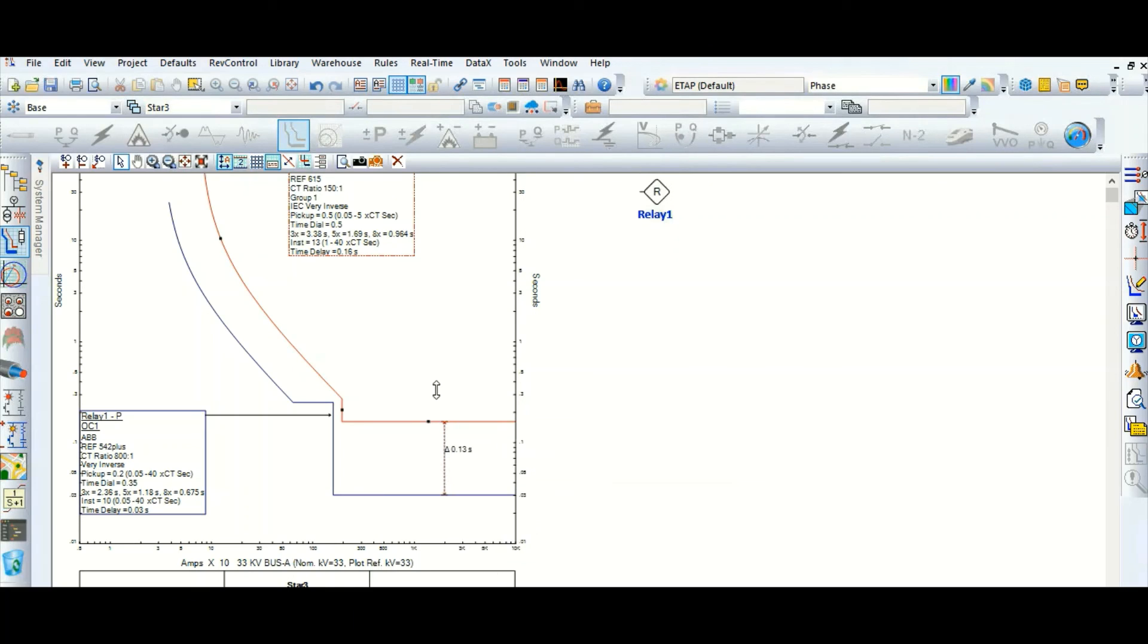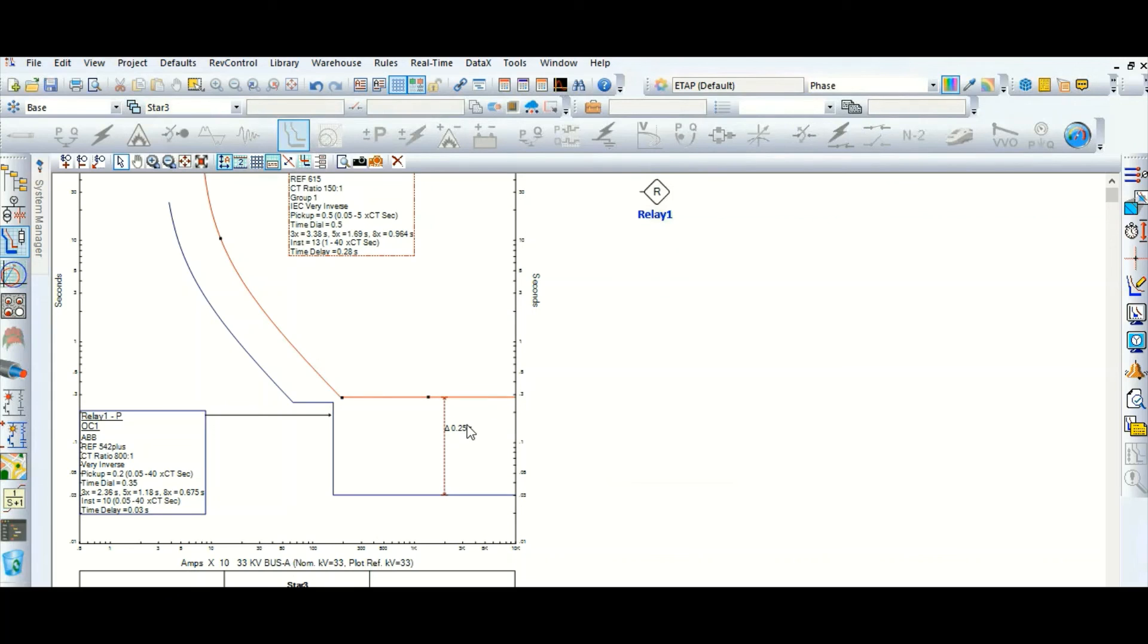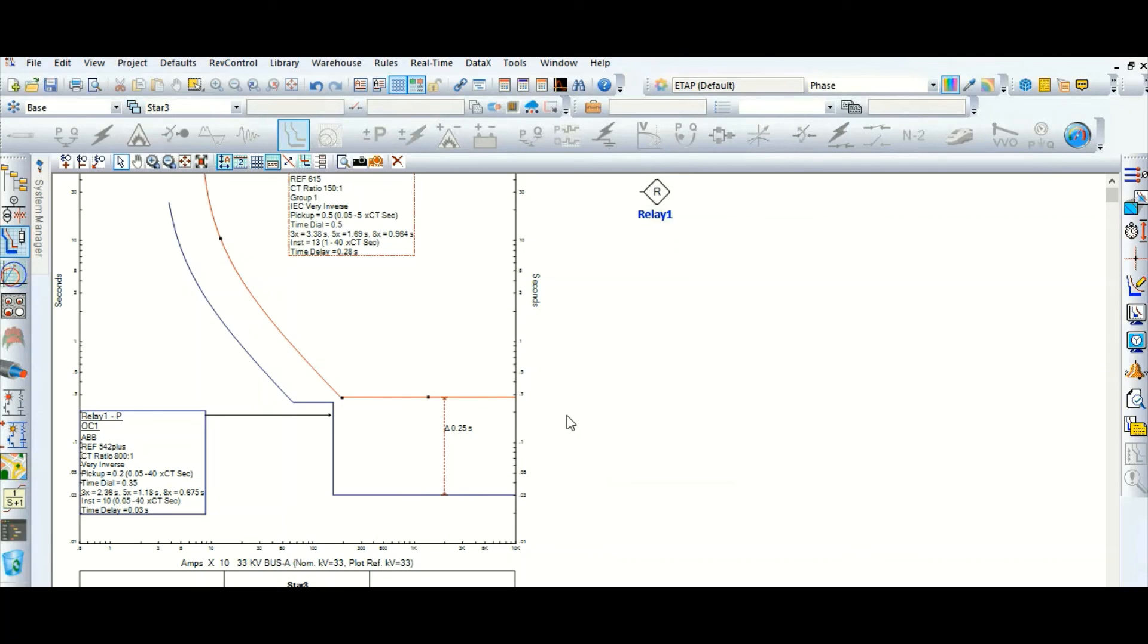If you want to give more, before going to this coordination you need to calculate manually, which we have not done in detail. So now this is 250 millisecond. This gap is 250 millisecond time discrimination between these two relay sensing. In the upcoming videos I will calculate first manually and after that I will put those input in the ETAP software. So up to this in this video.